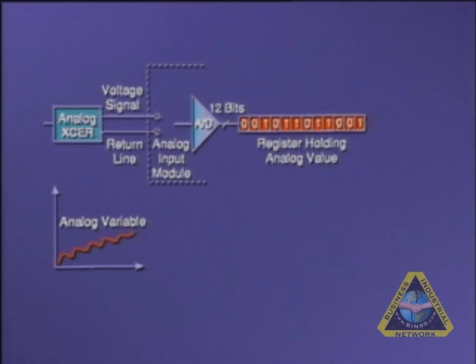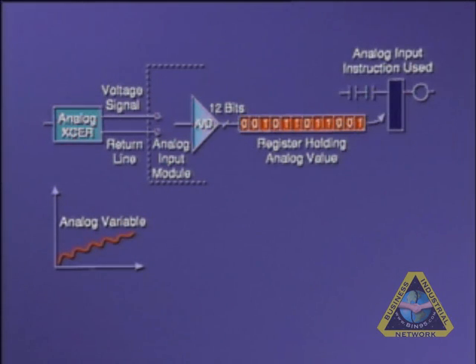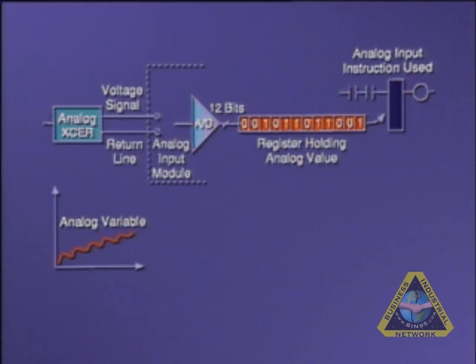This value is placed in a holding register inside the module, which will transfer the value once the appropriate instruction is executed during the program scan evaluation of the ladder control program. The instruction will transfer the numeric analog value into a register as specified by you in the analog input instruction used.